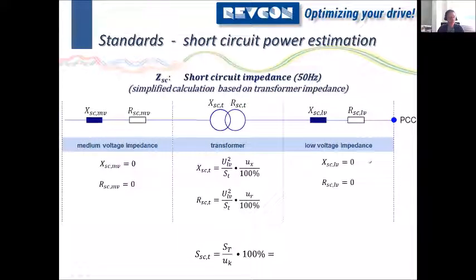So what you can do is you can make a simplified calculation. If you assume that your medium voltage impedance is not very relevant, which you should be careful about, especially in South America, because I know they have very long medium voltage distances, you can still take the transformer information using this equation to get the same ratio or to get the short circuit power of the transformer. And you could assume that this is the most relevant part, and then you can create your relationship with this part only. It's an estimation.